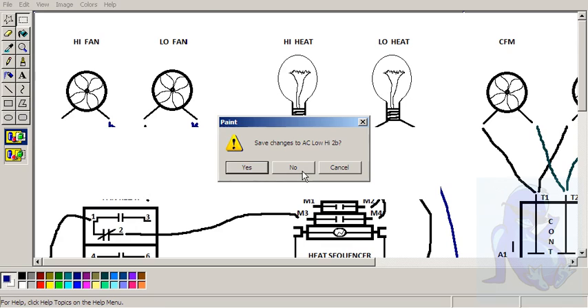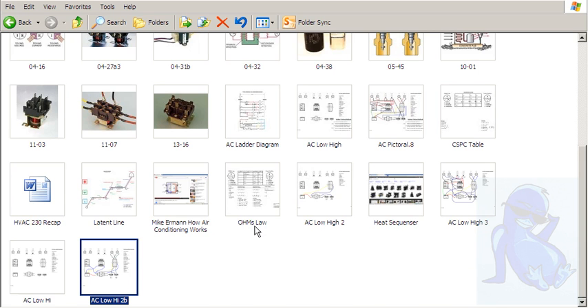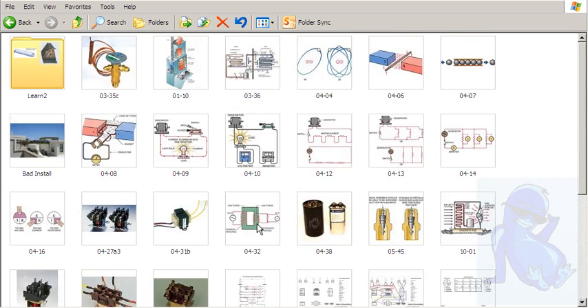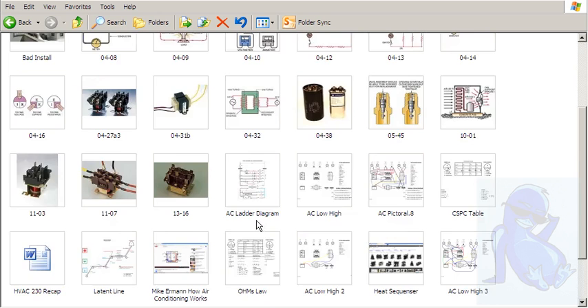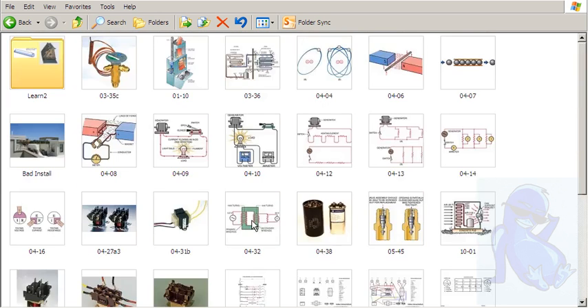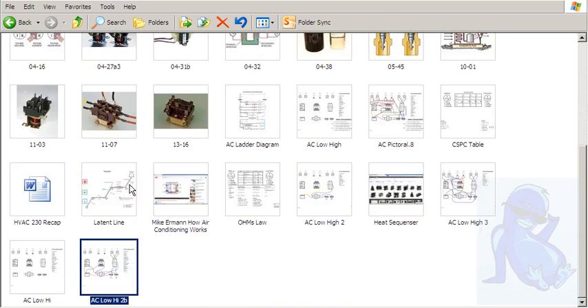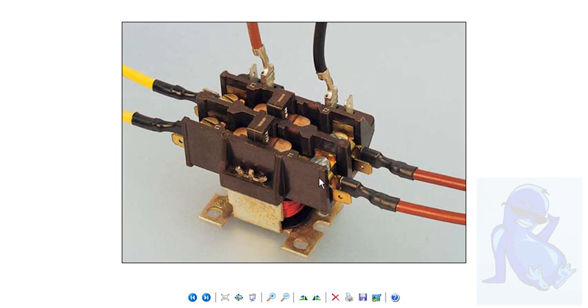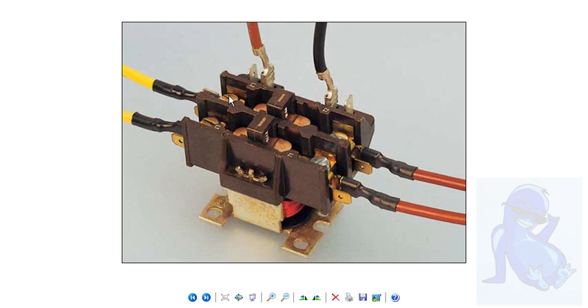Disconnect the power and try hooking up your wires. Take out your components. Pull out your contactor. See if it's good and clean. Maybe get you a little brass wire brush. Like a little brass toothbrush and just clean those components. Dirty contactors.